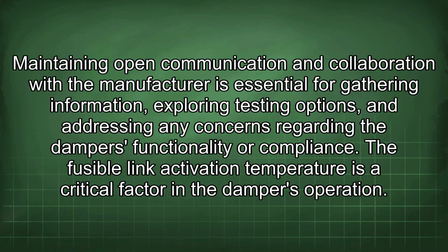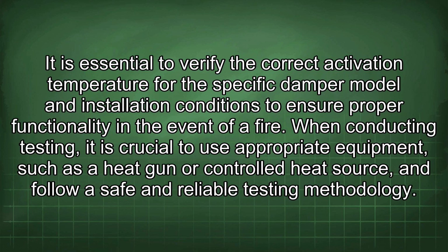Maintaining open communication and collaboration with the manufacturer is essential for gathering information, exploring testing options, and addressing any concerns regarding the damper's functionality or compliance. The fusible link activation temperature is a critical factor in the damper's operation. It is essential to verify the correct activation temperature for the specific damper model and installation conditions to ensure proper functionality in the event of a fire.